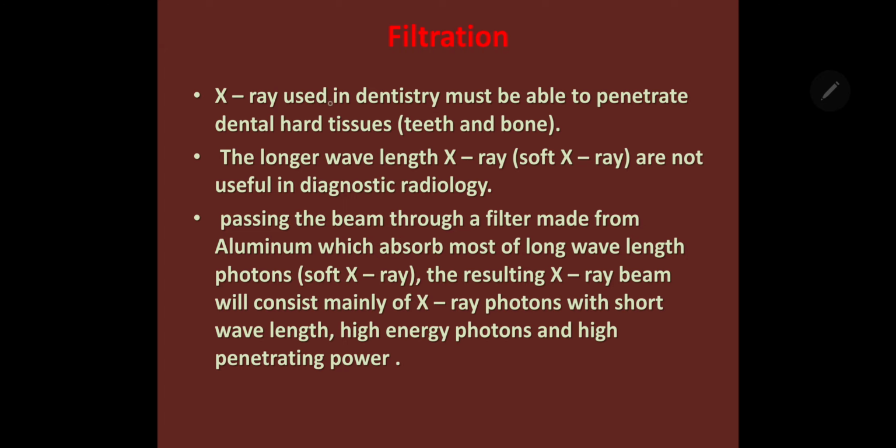Filtration. X-rays used in dentistry must be able to penetrate dental hard tissue, teeth and bone. The longer wavelength X-rays, soft X-rays, are not useful in diagnostic radiography. Passing the beam through a filter made from aluminium absorbs most of the long wavelength soft X-rays. The resulting X-ray beam will consist mainly of X-ray photons with short wavelength, high energy, and high penetrating power.